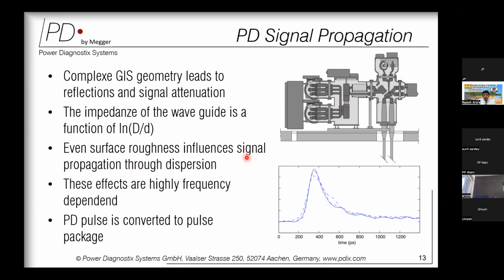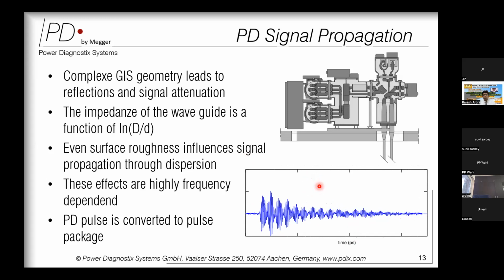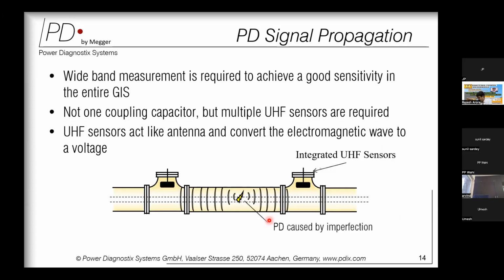Even the rough surface influences the signal propagation through dispersion. So the net effect is that the GIS partial discharge, which should have been a nice single pulse, results in pulse packets due to these reflections. And these effects are highly frequency dependent. That means a certain portion of the GIS will reflect certain frequencies, and hence this PD pulse is converted into a pulse packet. So it is not a single pulse, it is a packet of pulses.